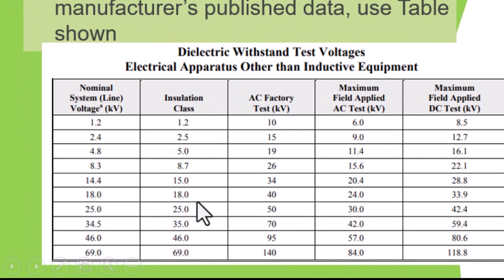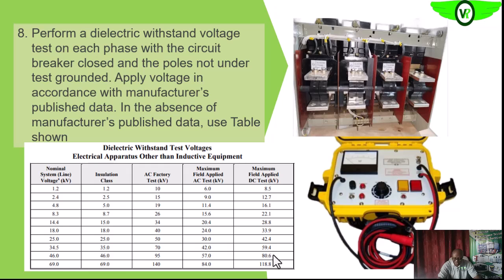You see that we use a voltage higher than the operating voltage of the equipment, subject it to a very high voltage, and then see that the insulation is able to withstand that particular voltage. If it can withstand that higher voltage, of course it means that the insulation will perform properly when subjected to the nominal voltage. We want to be very careful, because if the insulation is weak, it can be destroyed; in most cases the test could be destructive. So we want to follow the instructions already laid down in our facility. That is what we want to do during these dielectric withstand tests.